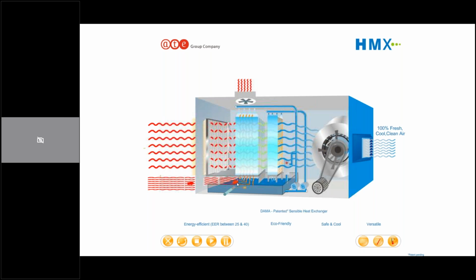It works well when you have a waste stream available with you. But if you're going to generate steam or heat for operating a VAM, it's never going to be viable. So if you have a waste stream, like in a power plant or something, and you anyway have a low pressure steam available that you need to discharge somewhere, it's a good application for a cooling system. Or if you have solar energy available and your air conditioning needs are during that time and the solar energy can meet them, I would definitely suggest it would be a good scenario to work with, because then your electric energy is not even 10%. Only the pumping energy is electrical.